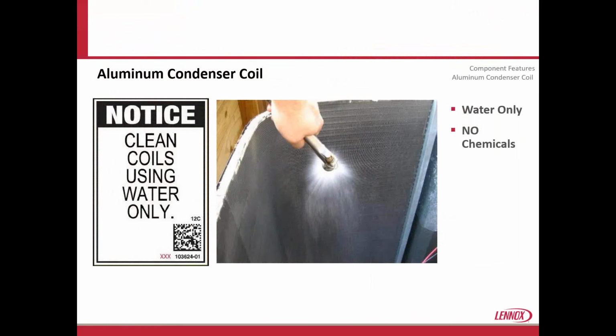Be sure to use water only. No chemicals are allowed on our equipment as far as the aluminum coils are concerned. If we have to use a cleaner or something, we want to make sure that it's a cleaner that's pH neutral and is designed for aluminum. There will be times throughout the life of a unit that at some point you will have something that has a leak, and it's going to have refrigerant coming out and oil coming out. It's going to hit the coil, and you have to clean it with something other than just water. But the normal maintenance of this unit is water only.